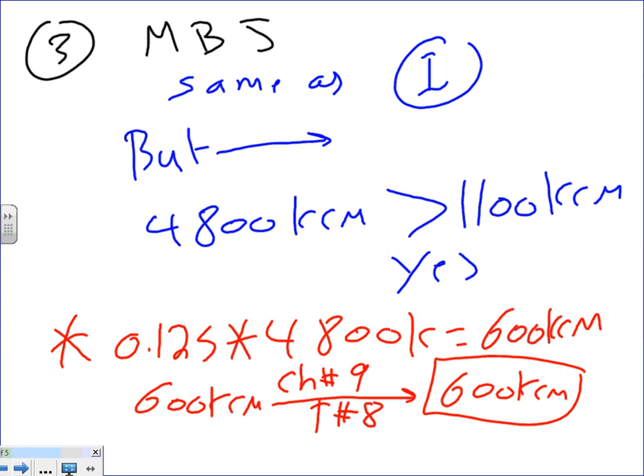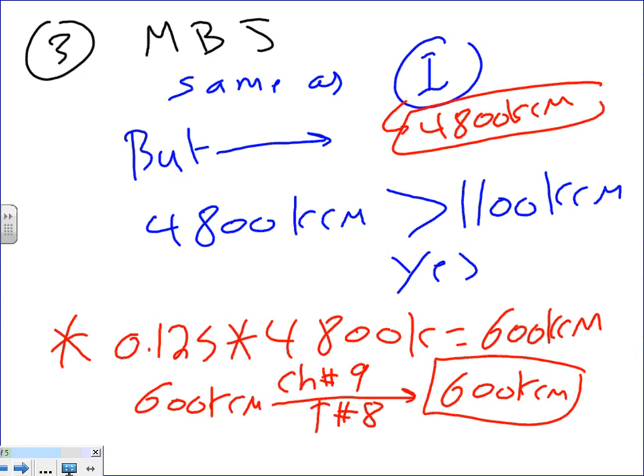Remember how we did the calculation? 4,000 divided by 12. Yes, 333 amps. Up to this point, I'm finding 4800 kcm is the same up to here. Then you apply this step. Everybody's getting that one, guys? You do the same as 1 as you find the 4800 kcm. Then if it's more than 1100 kcm, as it's telling you on the sheet that I gave you guys, you have to multiply by 12.5%.